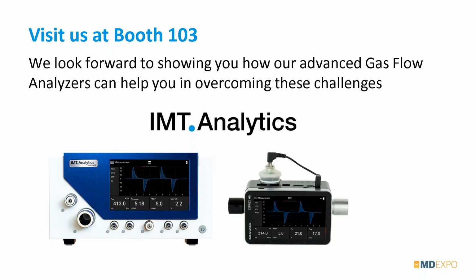So just from all the tech support that we do, some things that we hear a lot, I always tell people, make sure you warm up your device, your analyzer, give it at least 5 minutes. If you're traveling around and it's been out in the cold, let it warm up to room temp before you even turn it on. Then zero it out. In almost all analyzers, there's an auto or zero calibration that you can do. Make sure you zero it out so you're starting from baseline. Then do your gas standards and gas types. And lastly, trigger. And that takes care of, as Daniel said, probably 98% of the problems that we see out there.